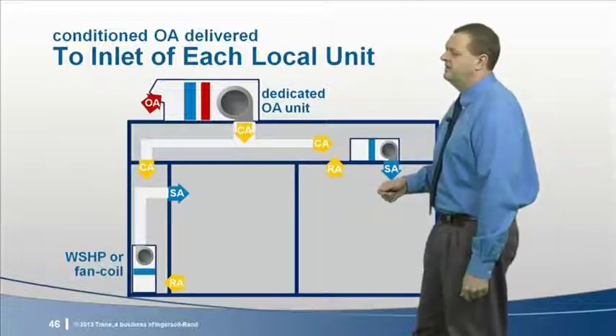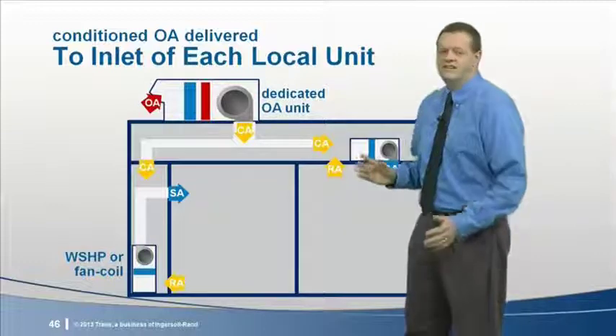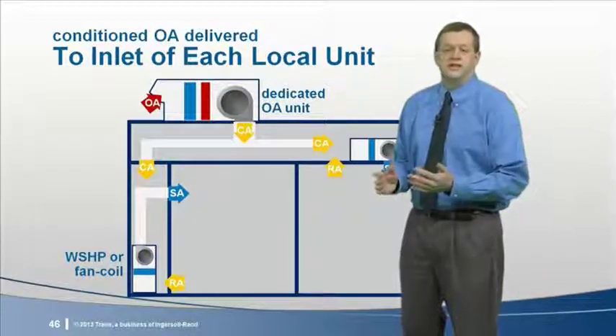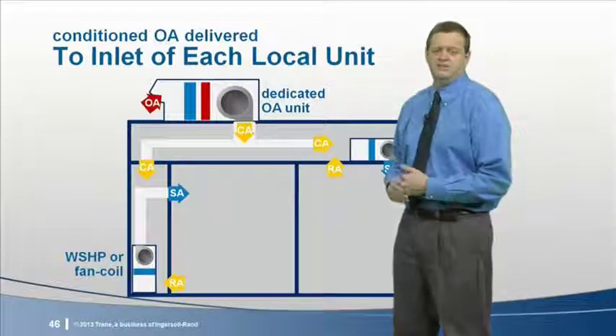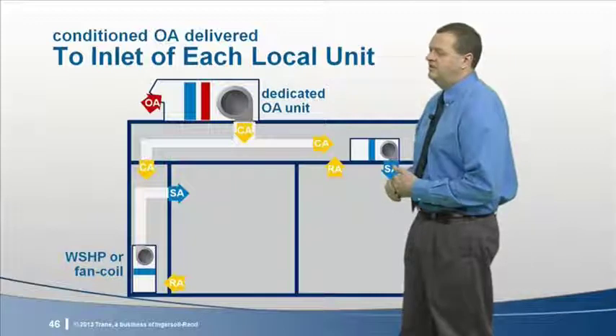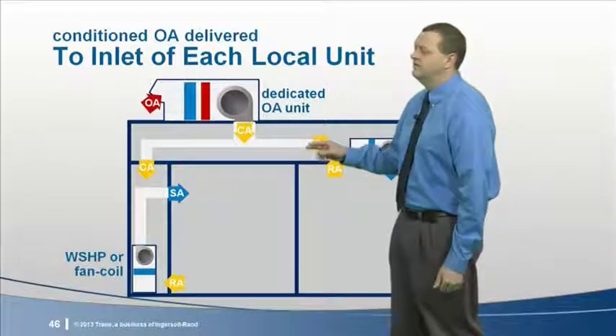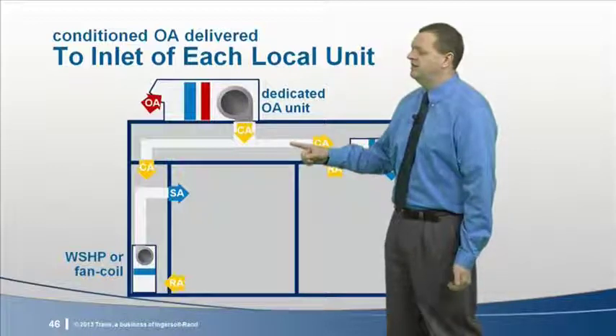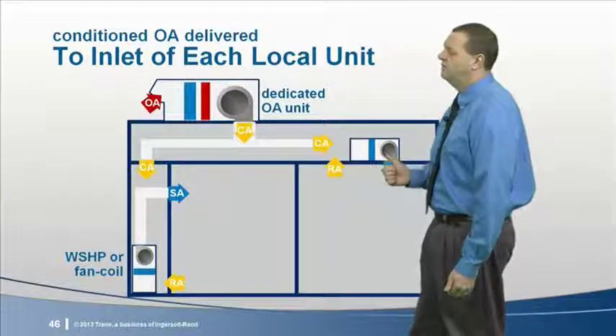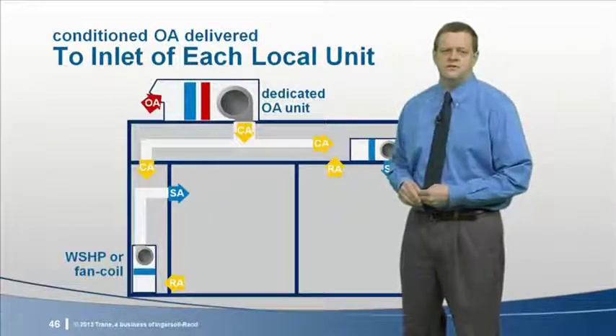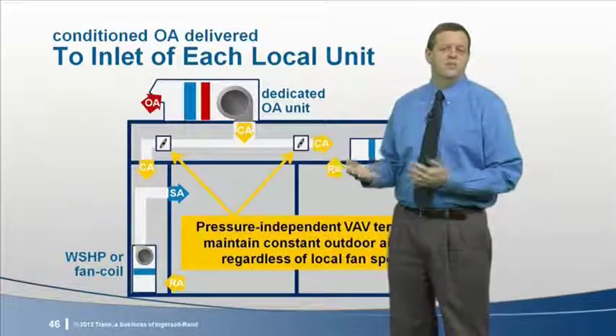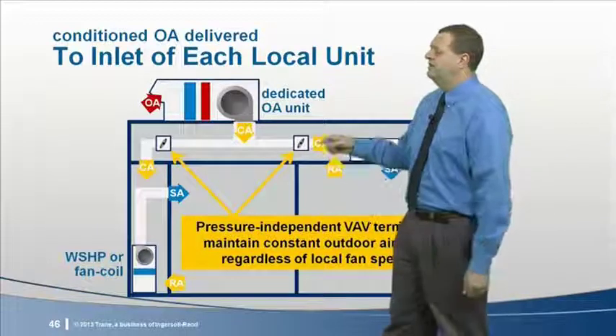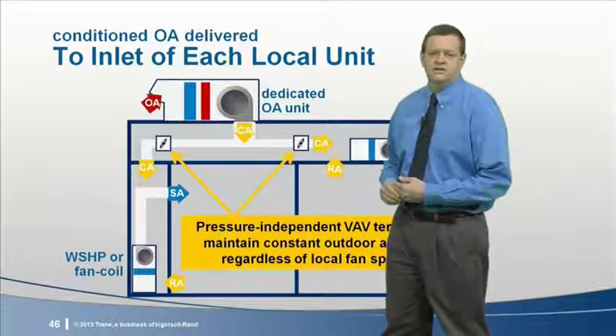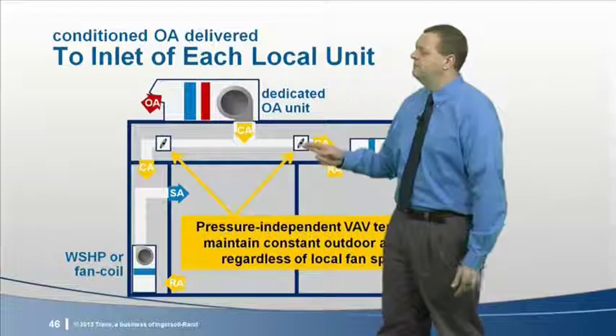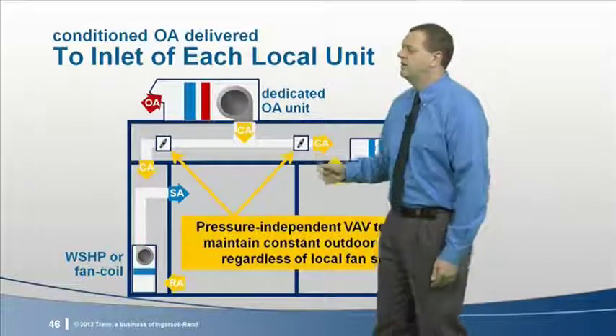Just like I described earlier, if this local unit has a 2-speed or a variable speed fan, the static pressure at the inlet is not as negative when fan speed is reduced. So again, outdoor airflow will decrease as supply airflow is reduced. An added challenge is that the outdoor air is delivered to this point by a separate fan, and the pressure in this ductwork is influenced by the changing operation of all the local fans served by this ventilation system. With this configuration, to ensure you get the required outdoor airflow, you should add a pressure-independent VAV box to the ventilation duct for each zone. Then as the fan speed changes, this damper modulates to maintain the same CFM of outdoor air regardless of fan speed.